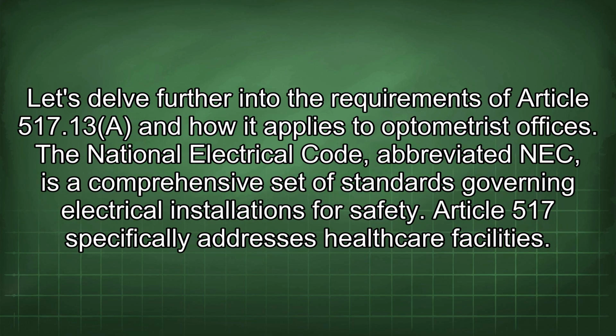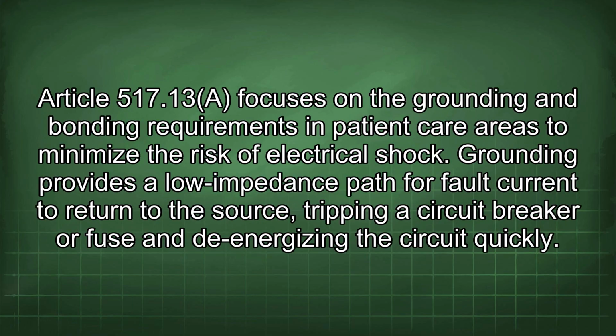Let's delve further into the requirements of Article 517.13 and how it applies to optometrist offices. The National Electrical Code, abbreviated NEC, is a comprehensive set of standards governing electrical installations for safety. Article 517 specifically addresses healthcare facilities. Article 517.13 focuses on the grounding and bonding requirements in patient care areas to minimize the risk of electrical shock.